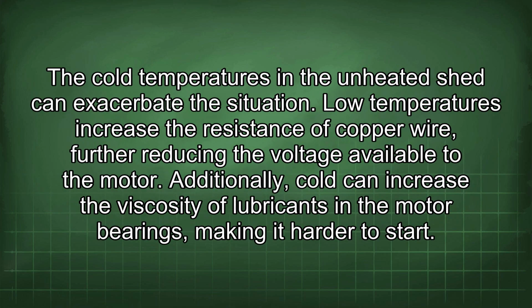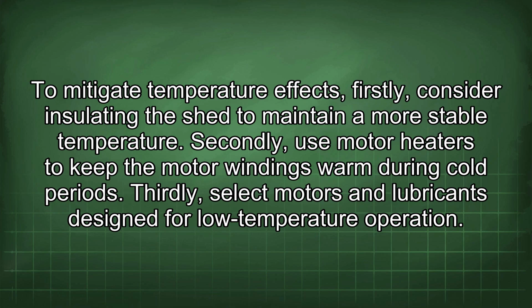The cold temperatures in the unheated shed can exacerbate the situation. Low temperatures increase the resistance of copper wire, further reducing the voltage available to the motor. Additionally, cold can increase the viscosity of lubricants in the motor bearings, making it harder to start. To mitigate temperature effects, firstly, consider insulating the shed to maintain a more stable temperature. Secondly, use motor heaters to keep the motor windings warm during cold periods. Thirdly, select motors and lubricants designed for low temperature operation.